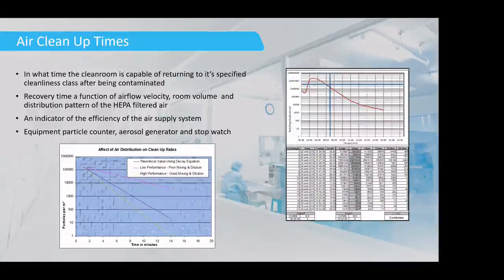So next we're going to look at air clean-up time. It's all well and good preventing particles from entering and filtering them out of the air, but it's no good if there's a source of contamination and it takes several days to clean up. So usually when the facility is first built, we go through an operational qualification where we'll artificially contaminate the space and then record how long it takes to clean up or scrub down that space.